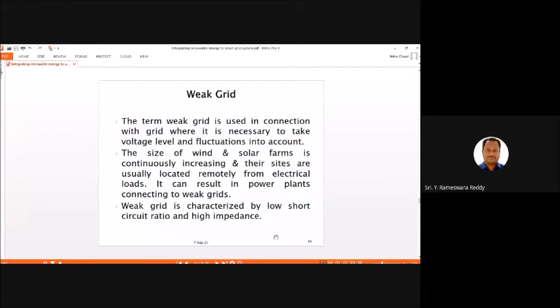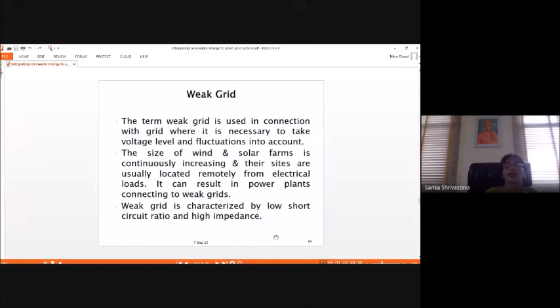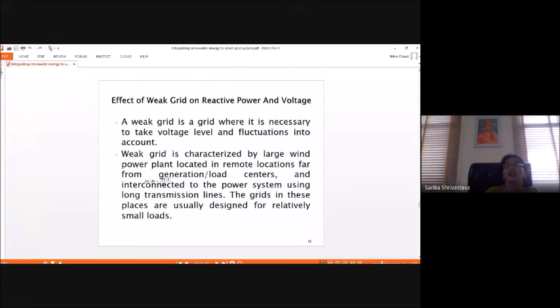Another scenario is the weak grid, where we need to take voltage and other fluctuations into account. The size of wind and solar farms is continuously increasing, becoming bigger day by day, and usually they are far from the loads. Power plants are installed where they get uninterrupted supply of everything—for wind, sites away from population for uninterrupted wind, and for solar, no shading. This results in connecting to weak grids, which are characterized by short circuit ratios and high impedance, requiring us to account for voltage and frequency fluctuations.